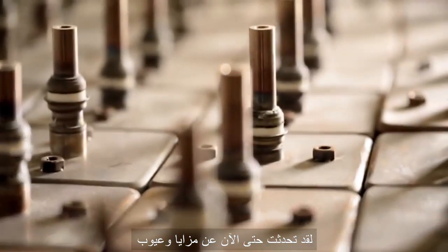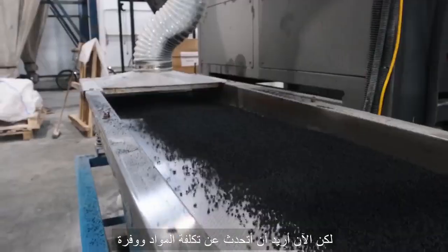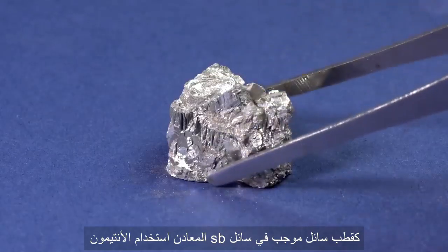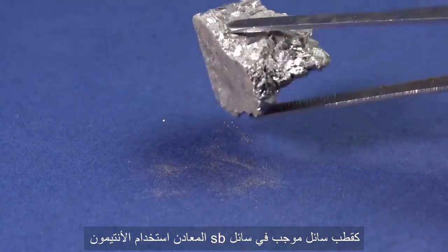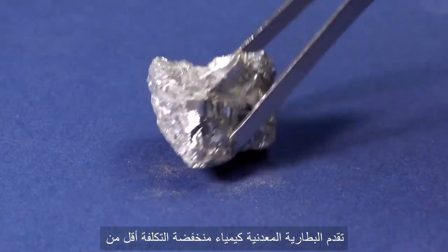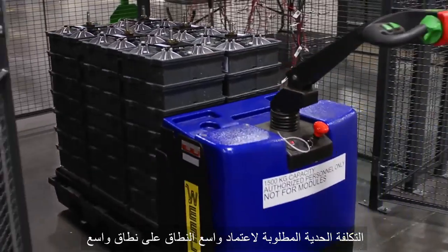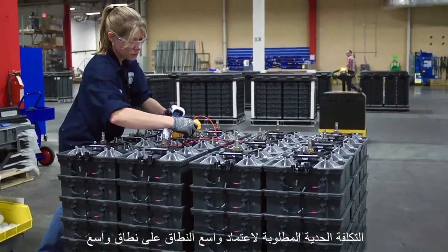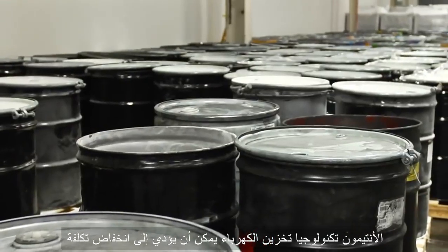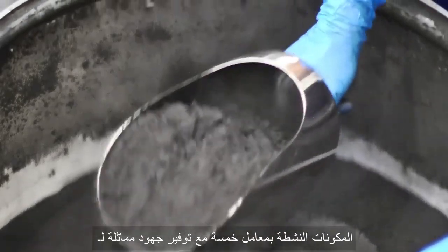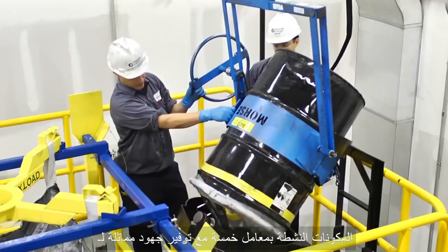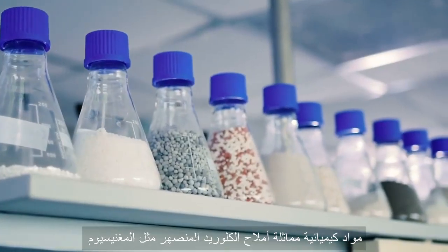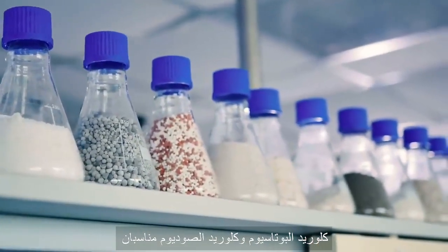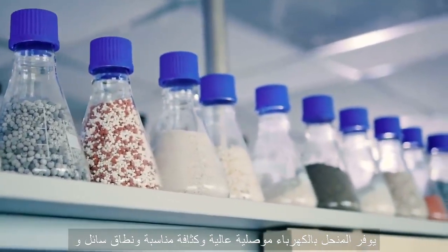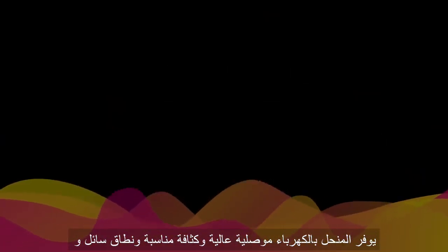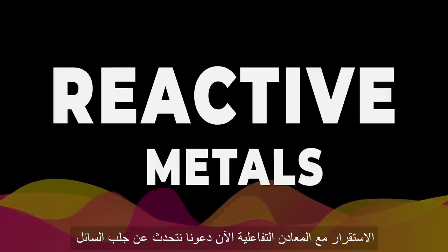I have spoken so far of advantages and disadvantages, but now I want to talk about the materials cost and abundance. Metals. The use of antimony, Sb, as the positive liquid electrode in a liquid metal battery offers a low-cost chemistry, below the threshold cost required for broad-scale adoption of a large-scale electricity storage technology. Antimony could potentially drop the cost of the active components by a factor of 5, while providing similar voltages for analogous chemistries. Molten chloride salts, such as magnesium chloride, potassium chloride, and sodium chloride, are suitable as the electrolyte, providing high conductivity, a suitable density and liquid range, and stability with reactive metals.